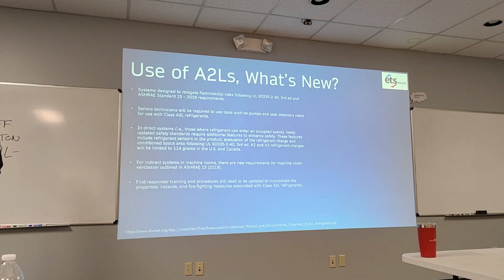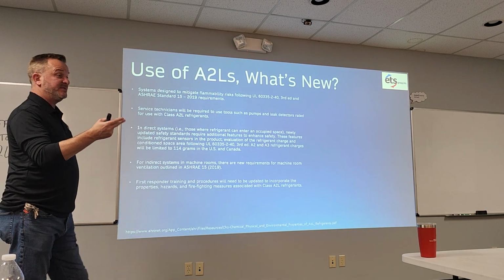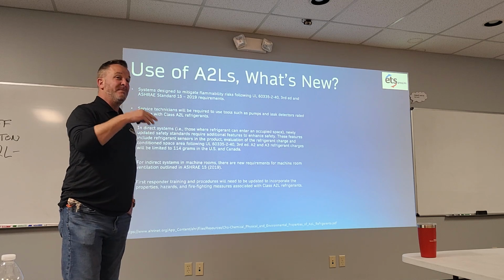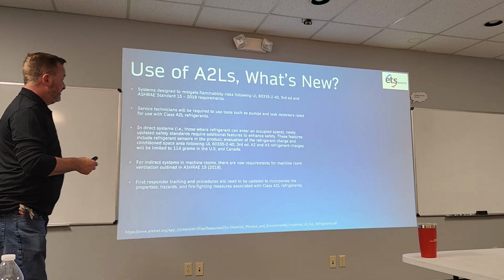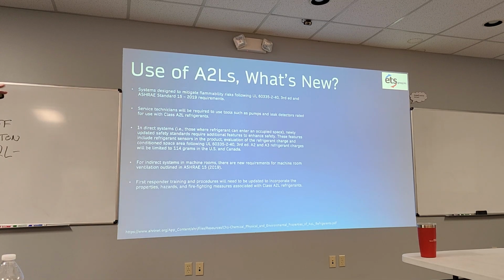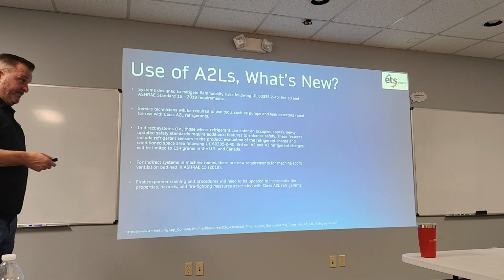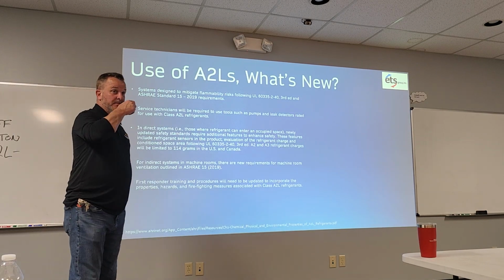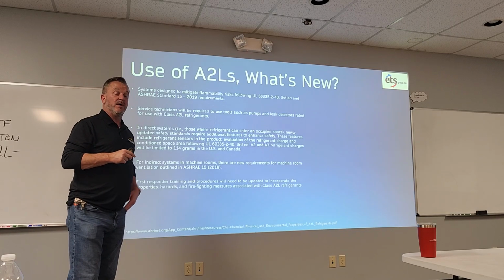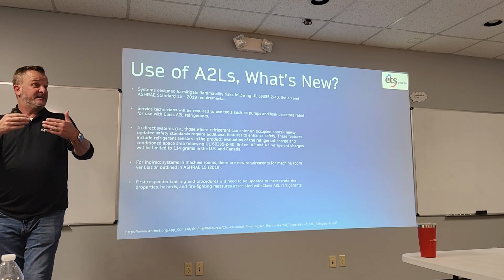These systems out there have either RDS systems, which are refrigerant detection systems, or mitigation systems. So that's why I say if it's a 454B system, you can only use 454B on there. Why? What is an RDS system? It's like a leak detection system, so every one of these systems are going to come with leak detection on it.